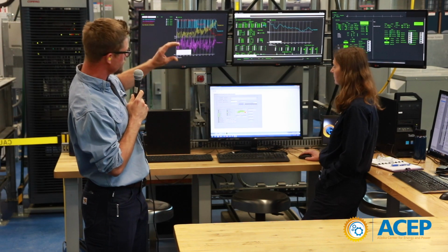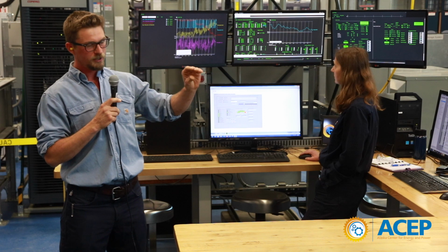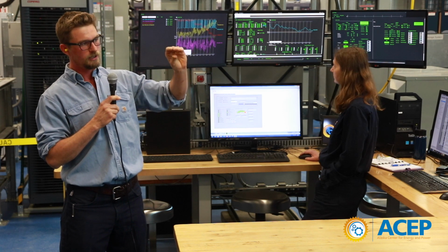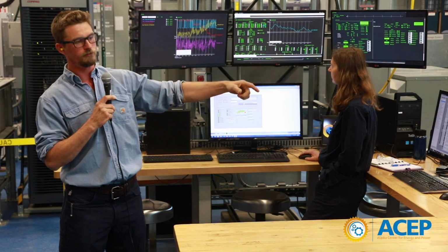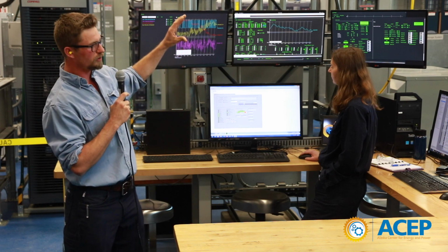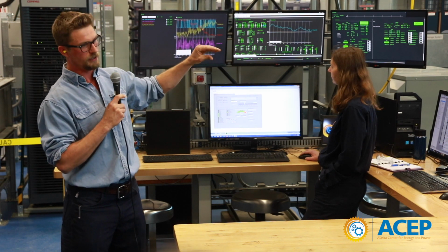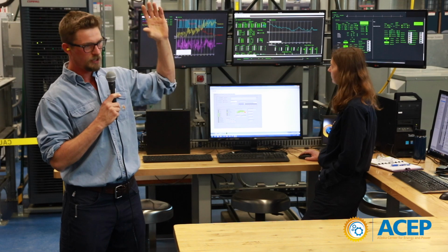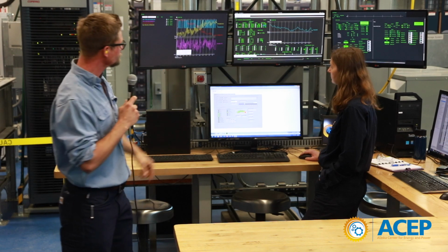We're going to reduce the load on our diesel generator, because you don't want to open a circuit breaker where there's a lot of current flowing through it. So we're going to slowly reduce the load the diesel generator is supplying, and then open up the circuit breaker and see what happens.